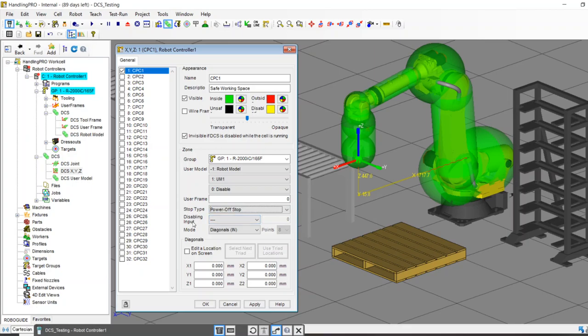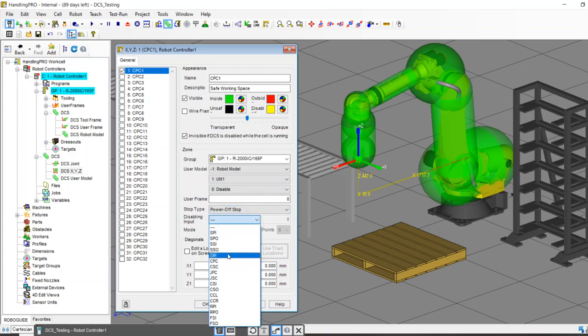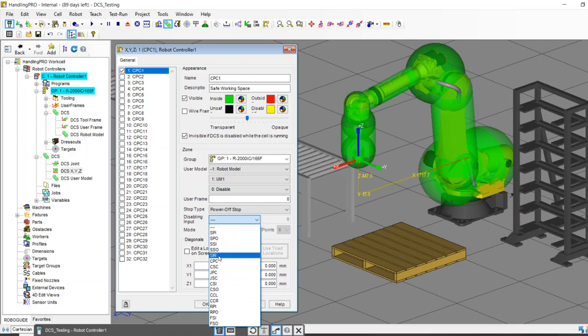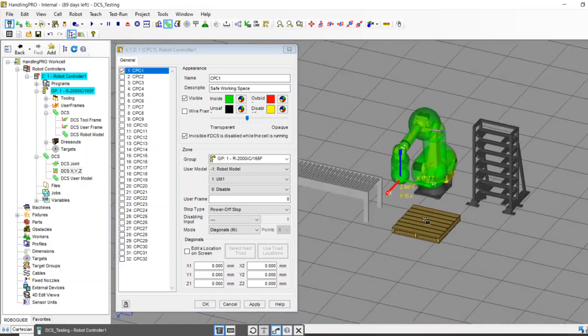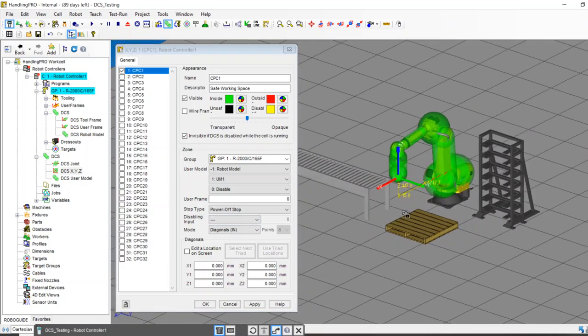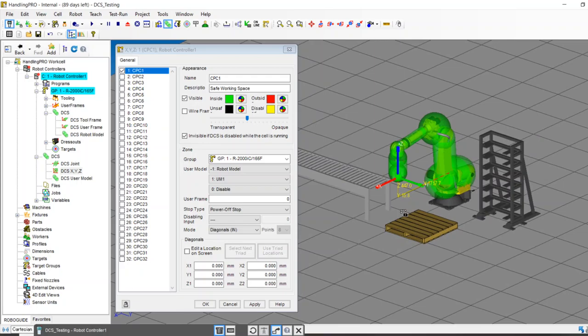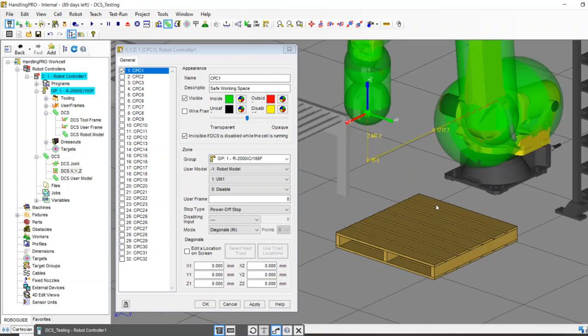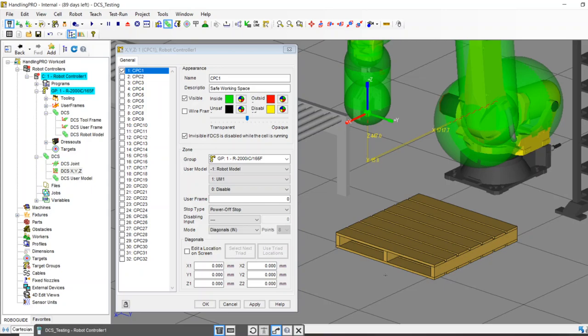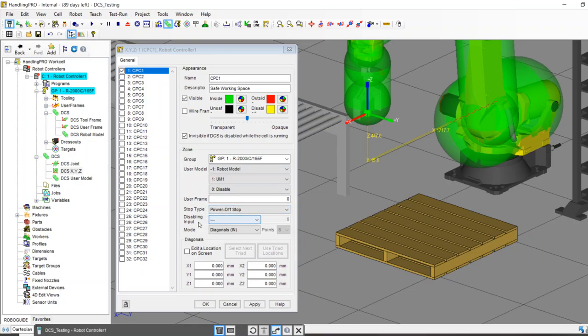Disabling input. That is an input that disables all your work. So as you look at this, there are a lot of different inputs. Odds are you would probably be using what we call an SIR. That is a safety input relay. These robots come with two safety inputs. They're dual channel. So there's four wires. And what you can do is you can wire a light curtain or an area scanner or something that says, hey, if there's nobody here, don't stop. Maybe someone has to come and get this pallet. So when there's a human in there, I want the robot to stop. And when there's not a human there, I don't want the robot to stop. So you can disable these CPCs based upon human presence by defining that and wiring something in.